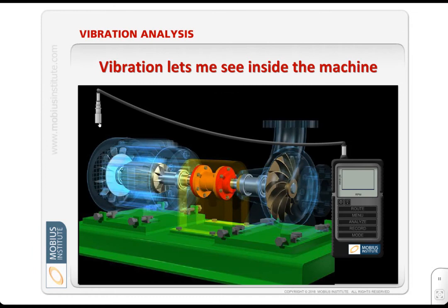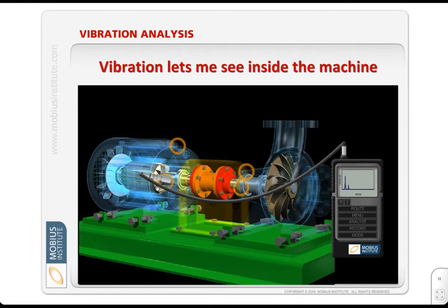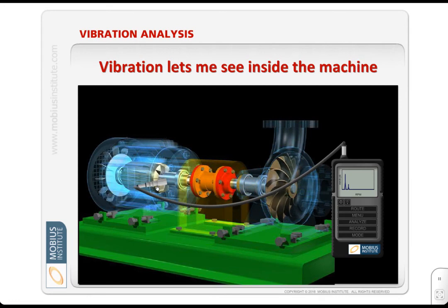And then we've got vibration analysis. We can put a vibration sensor on the machine and it will measure the up and down, the vertical vibration. Now, machines vibrate in 3 axes, so we also measure horizontally and axially along the length of the machine. It just depends if there's an unbalanced problem, a misalignment problem, a problem with the bearings, and so on. There's different places we take our measurements, and we can learn so much from even just an overall level, just a single number that represents the vibration. But gee, if we look at the spectrum, the time waveform, phase measurements, there's so much we can learn.